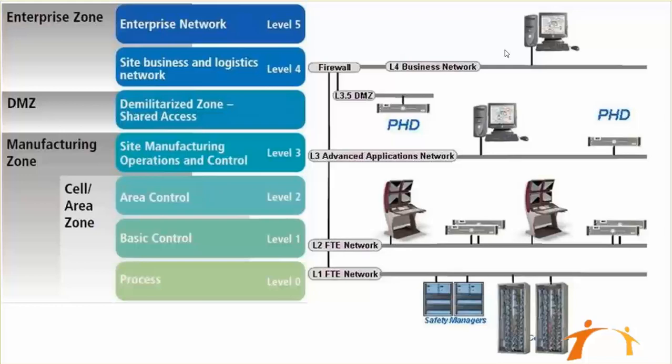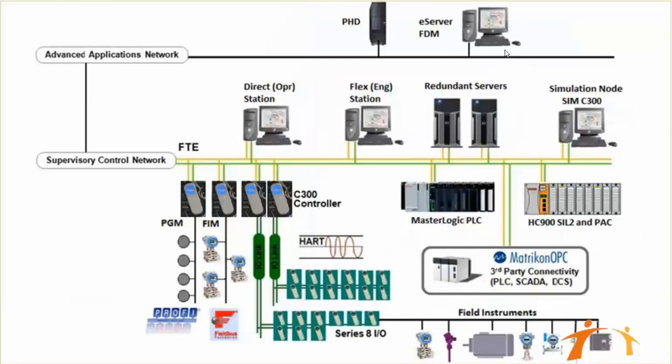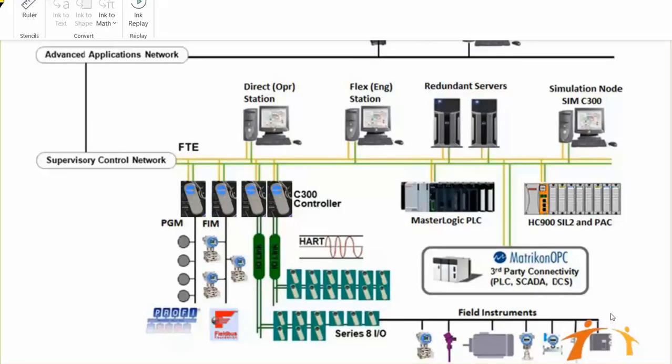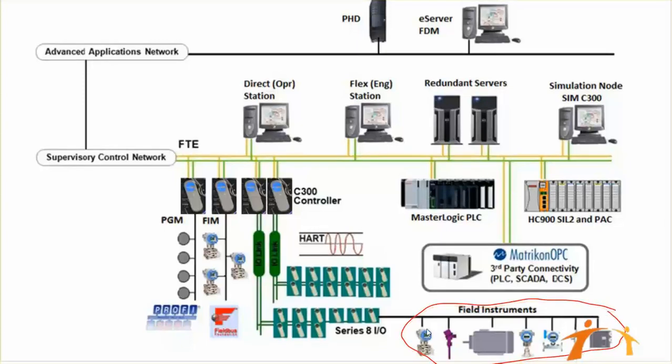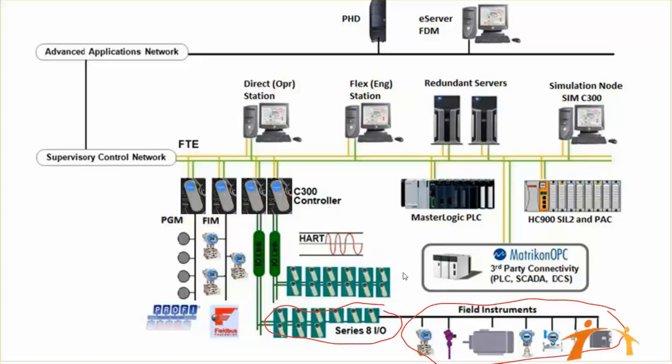Let's focus on our specific Honeywell DCS control system architecture. If you see here from the bottom, we have field instruments coming from the bottom, and those field instruments are connected to our IO modules. These are Series 8 IO modules, it could be Series C IO modules, and this is another Series 8 IO module. Those modules are connected to your controllers, your DCS controllers.